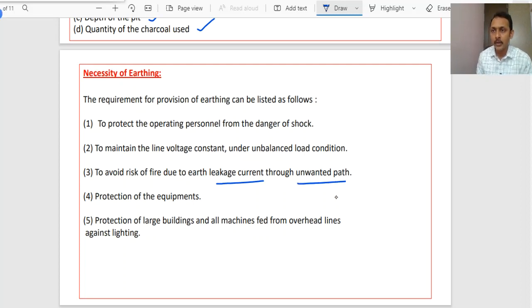If any leakage current passes through the equipment body, it leads to a rise in the potential of the equipment body. Then if a person touches that equipment, he will undergo electrical shock. So if the equipment is properly earthed, we can avoid electric shock. Also, earthing is useful for the protection of equipment, and of large buildings and machines fed from overhead lines, against lightning strokes. So this is the importance or necessity of earthing.